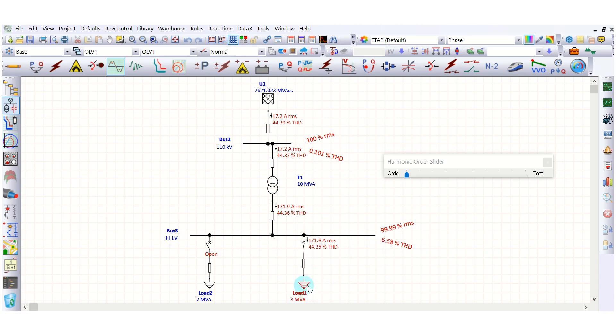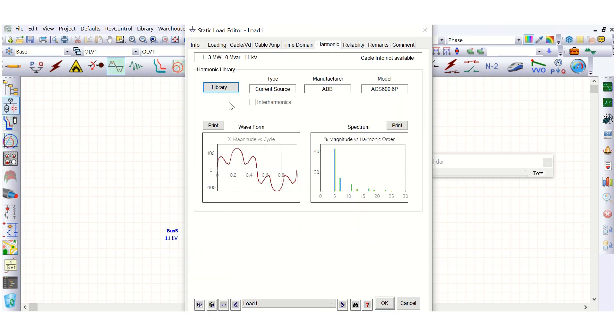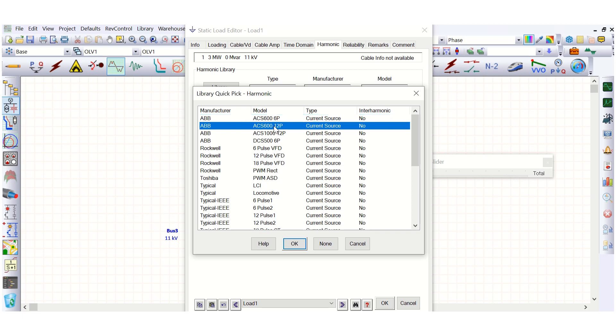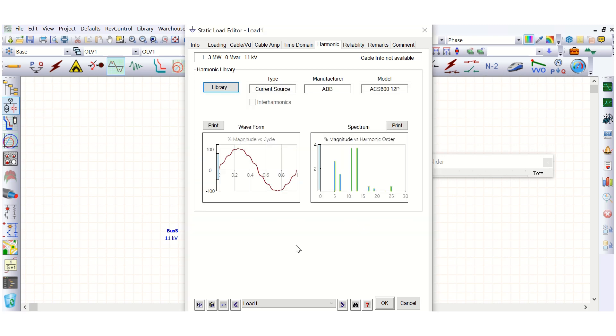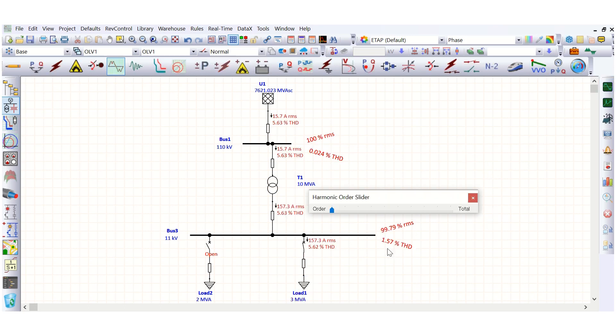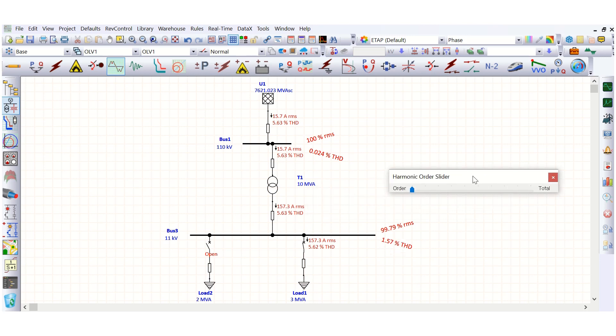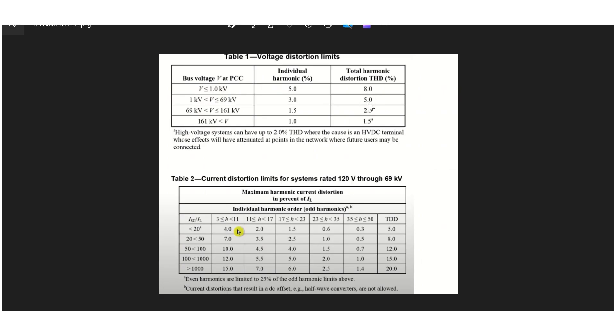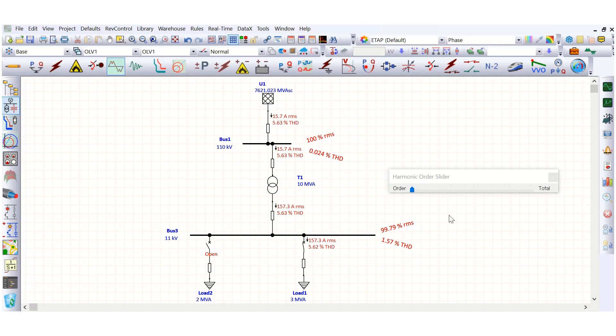To mitigate this, instead of the six-pulse harmonic model, we can use the 12-pulse model — the waveform will be improved and less distorted. Running the simulation again, the total harmonic distortion is reduced to 1.57%, which is well within the IEEE 519 requirement of 5%.